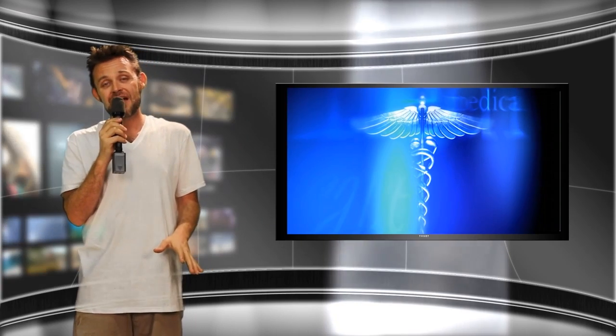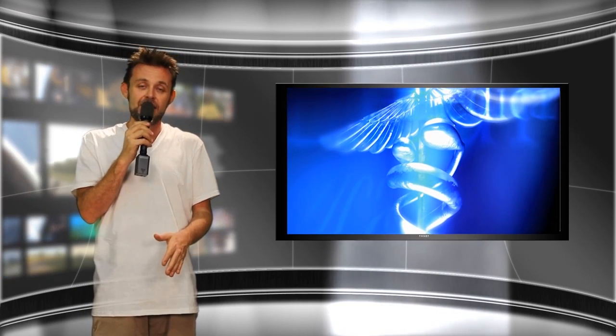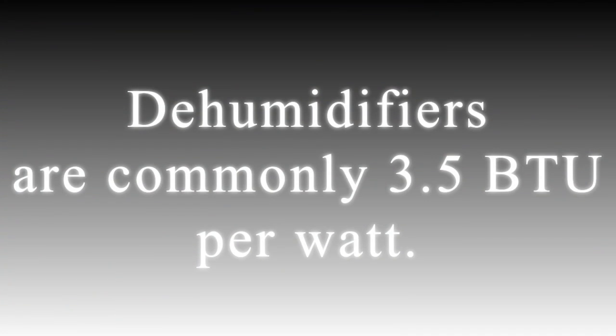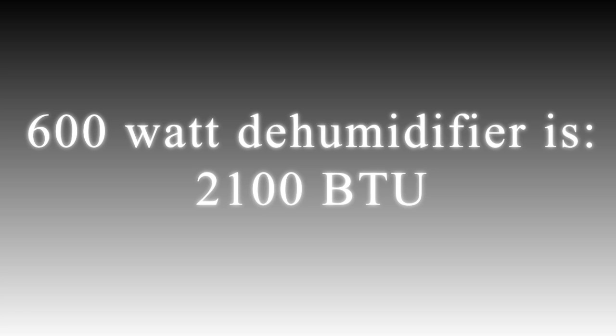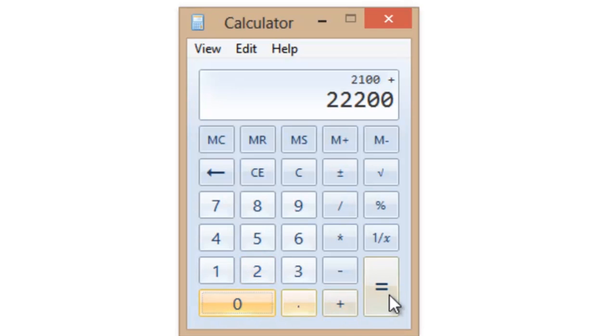The next thing we need to look at is our dehumidifier. This dehumidifier is 600 watts, and dehumidifiers are gauged much the same way as lighting except on the lower side of that threshold. Dehumidifiers are commonly about 3.5 BTU per watt, meaning this 600-watt dehumidifier will be 2,100 BTU. Adding that to our existing subtotal of 22,200 BTU puts us at 24,300 BTU.